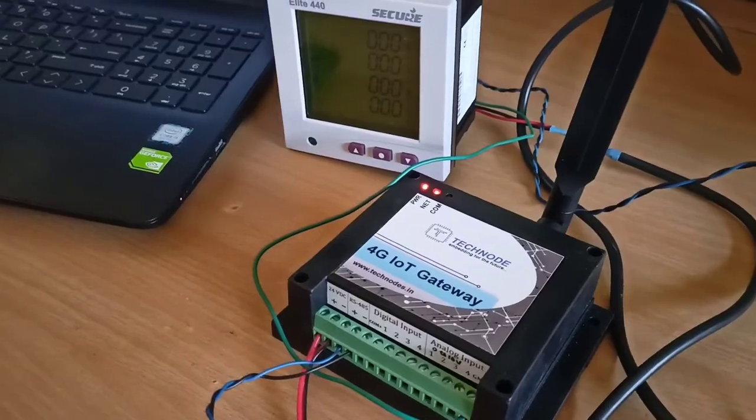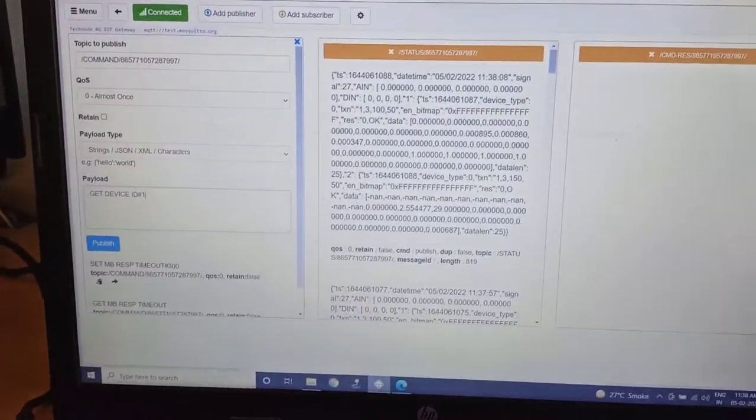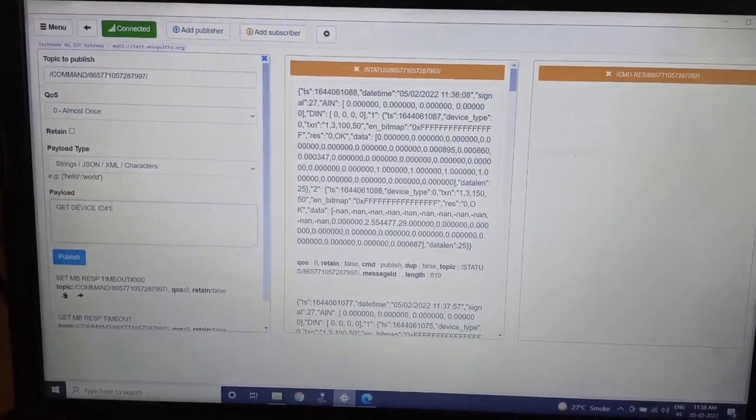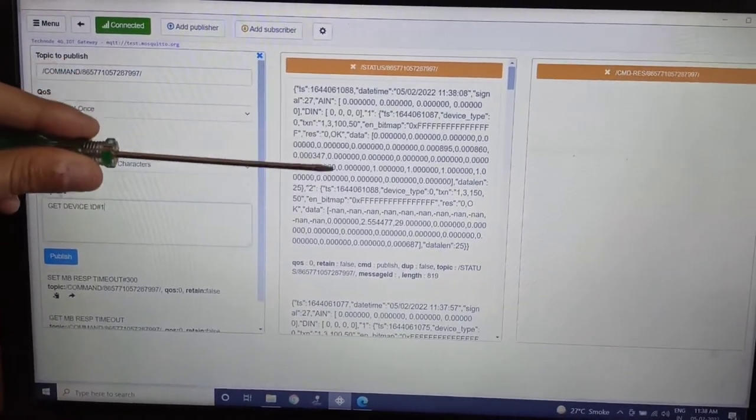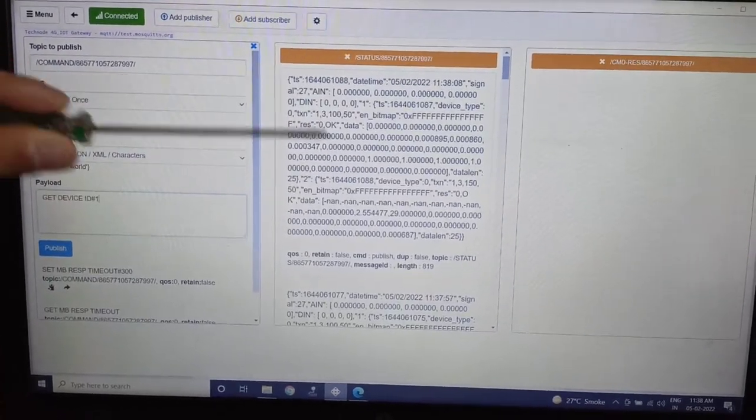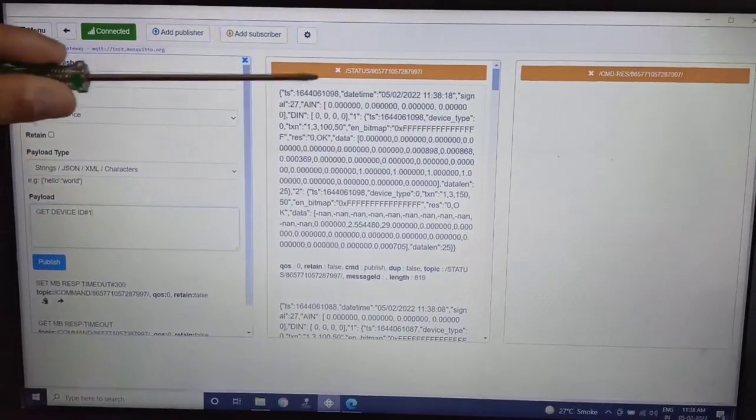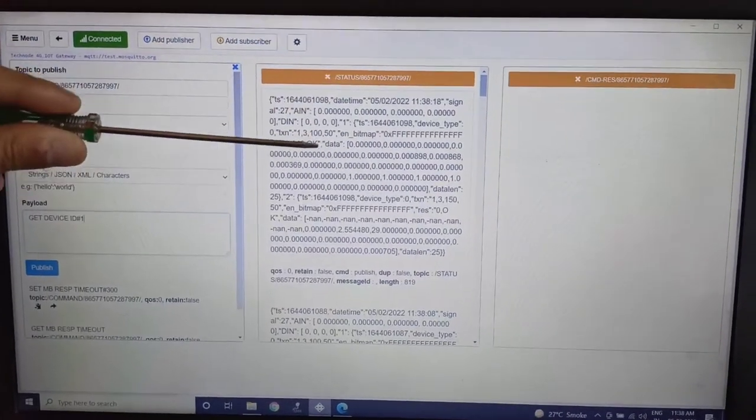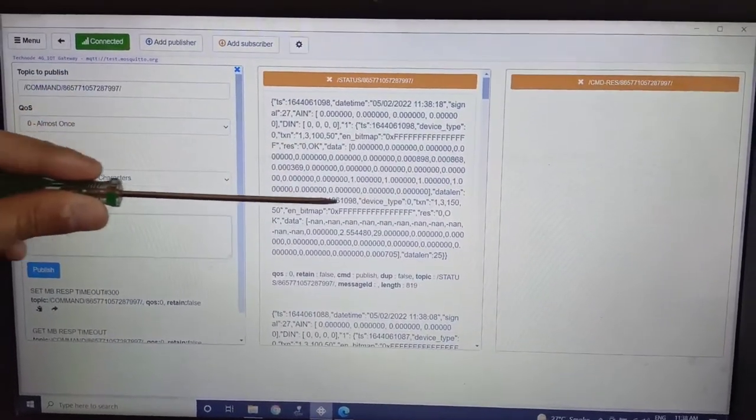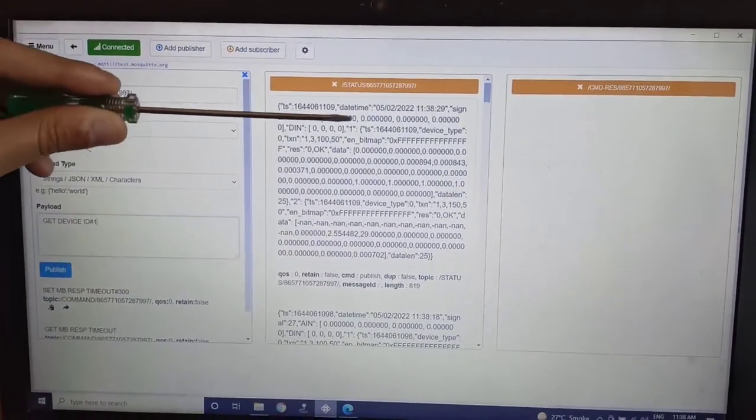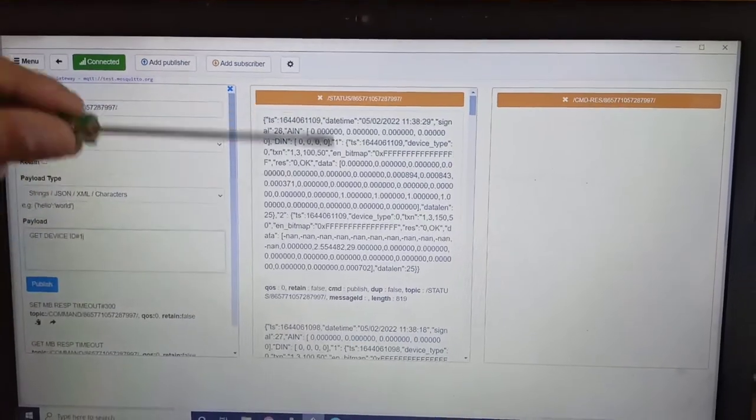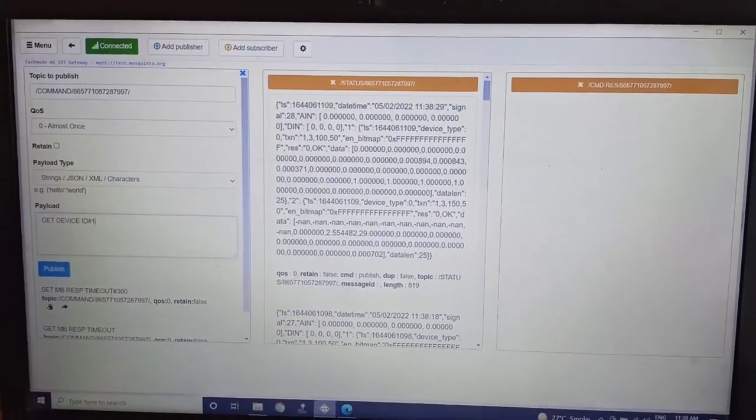So now coming towards looking for the data, I have connected here one application. So this application is basically an MQTT Box application. So here you can see the data is coming in the JSON standard key-value pair format. So in two curly braces and with comma-separated data, all key-value pairs like date and time, then timestamp, and all the values like 0, 0, 0, 0 as you can see. All values are zero because we have not connected any phases. Also, the values for digital and analog inputs are coming and the values are getting refreshed time to time.